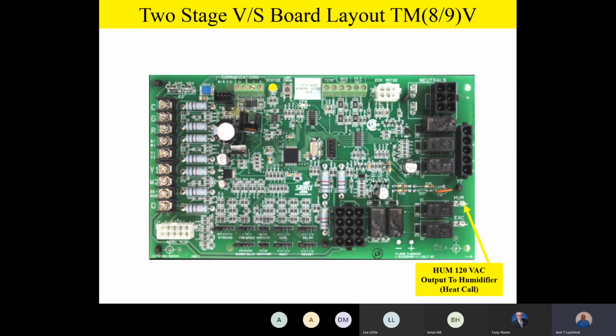And I like that because now you've got some isolated relay outputs. As a matter of fact, those 2 little black relays right beside those terminals, those are isolated, typically 1 amp, 120 volt relays, and they give you some nice isolation on the electronic air cleaner as well as the humidifier. And so right below that HUM terminal is our EAC output. Again, on our furnaces, that's 120 volt output. It's an electronic air cleaner terminal, and that will be energized by way of that isolation relay, I might add. Anytime you have a G call or anytime the fan is running, you'll have an output on that EAC terminal.